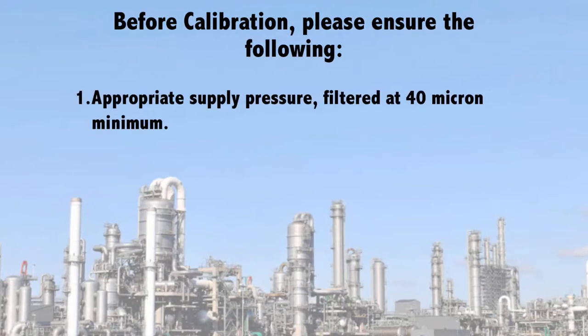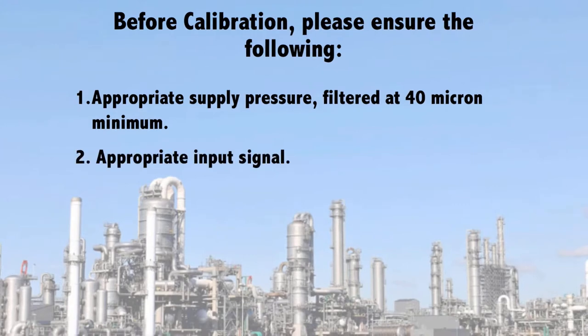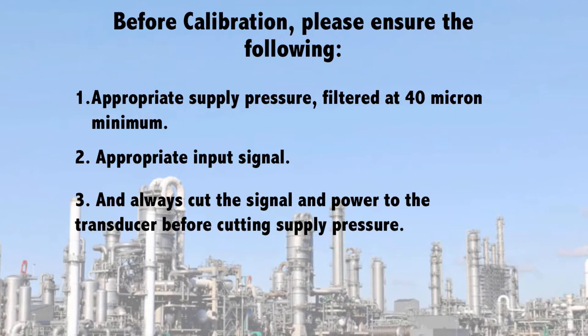Please ensure the following. Appropriate supply pressure, filtered at 40 micron minimum. Appropriate input signal and always cut the signal and power to the transducer before cutting supply pressure.